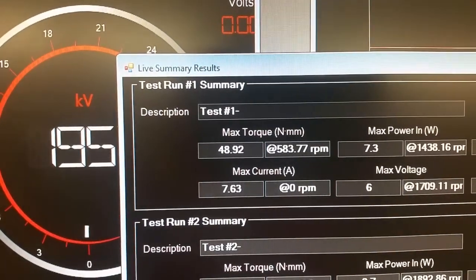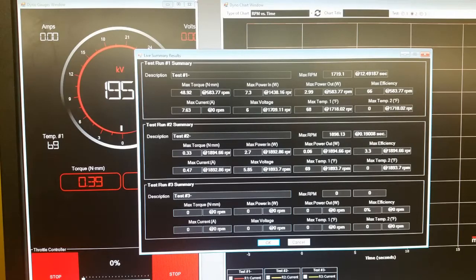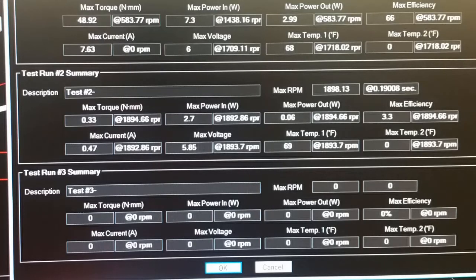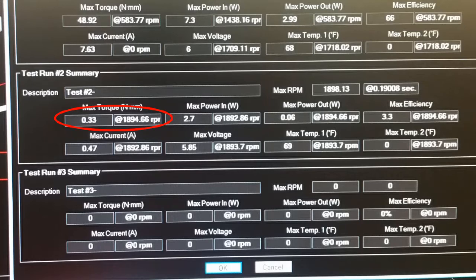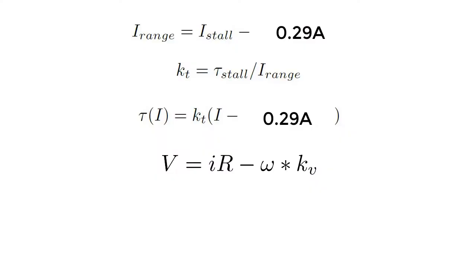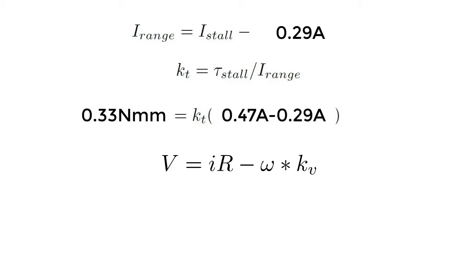This shows us a summary of what we captured in this test. Go down to test number two and look at the max torque. Since we only captured one particular operating value in test number two, the max torque is telling us the amount of torque that we had at a particular speed. Write down these numbers and we'll use them in our equations. Also write down the max current value. Fill in the torque and current values that we just wrote down here in this equation. This will allow you to solve for kt, the torque constant.